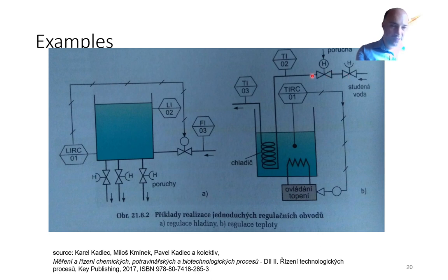I can close it also with this automated valve, but also with hand control. So I have redundancy here, two valves. I measure the temperature of the input water. I indicate it locally. I measure the temperature of my output water and I indicate it locally. So this is my feedback control. I'm controlling this, and this is just showing me the values on some panel meter.